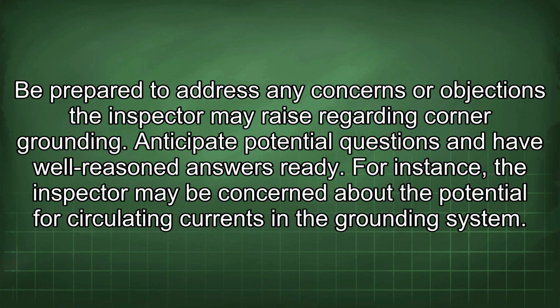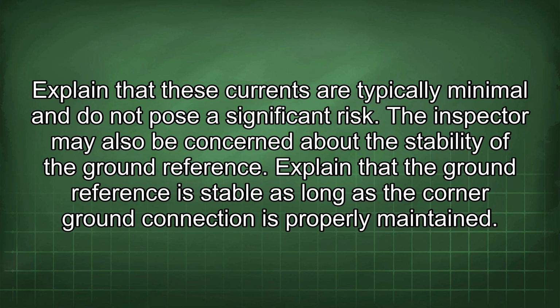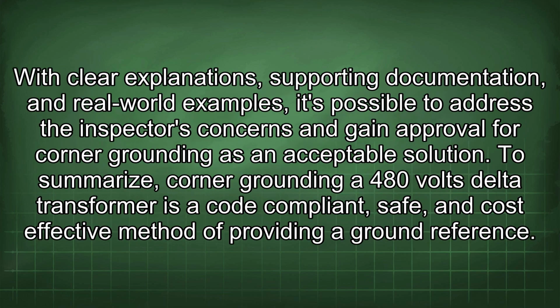Be prepared to address any concerns or objections the inspector may raise regarding corner grounding. Anticipate potential questions and have well-reasoned answers ready. For instance, the inspector may be concerned about the potential for circulating currents in the grounding system. Explain that these currents are typically minimal and do not pose a significant risk. The inspector may also be concerned about the stability of the ground reference. Explain that the ground reference is stable as long as the corner ground connection is properly maintained. With clear explanations, supporting documentation, and real-world examples, it's possible to address the inspector's concerns and gain approval for corner grounding as an acceptable solution.